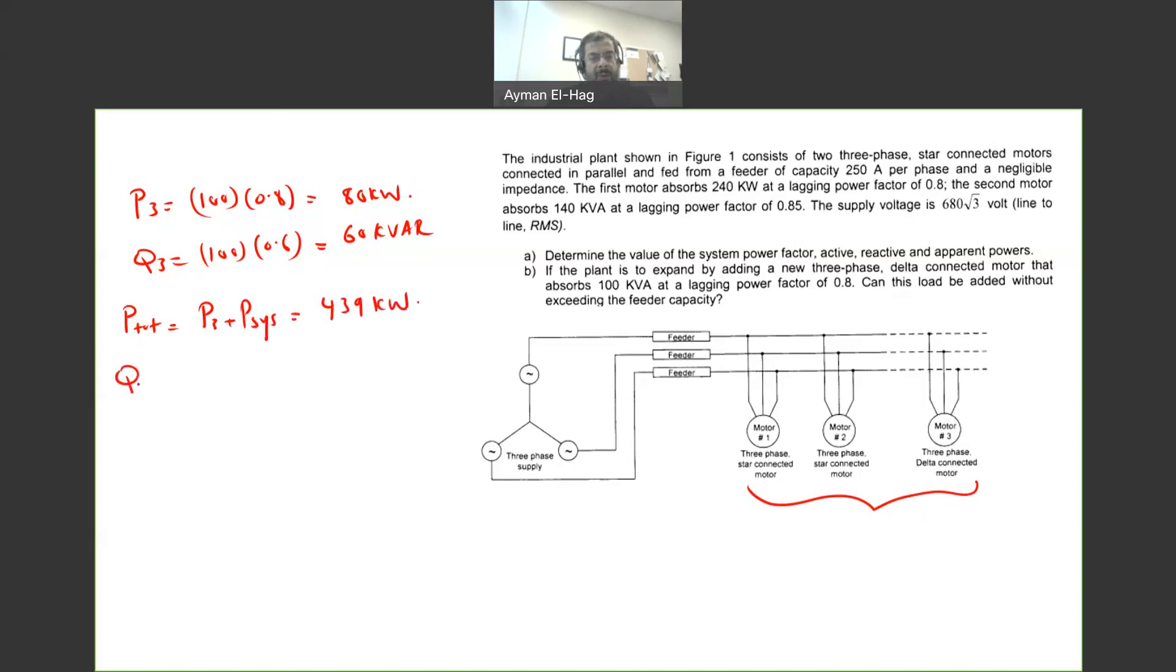And my Q total is equal to my Q3 plus Q of the system, and this gives me 313.75. From this, you can find your S. Your S total is equal to P total square plus Q total square, and this will give me a total kVA of 539.89 kVA.